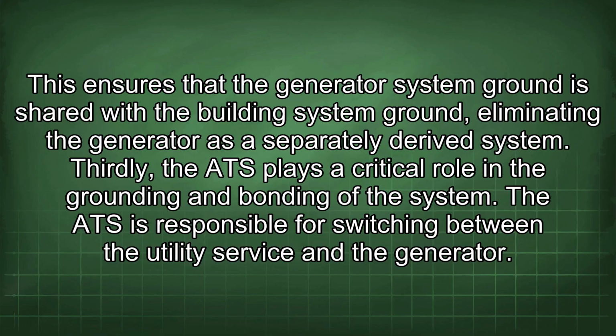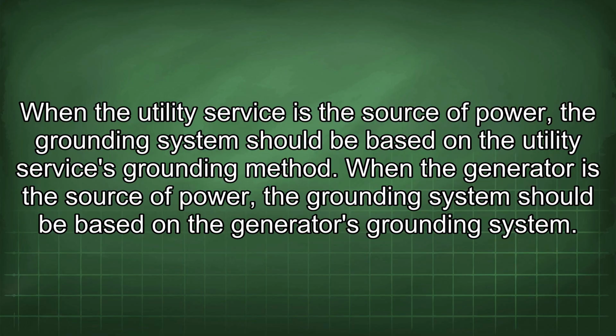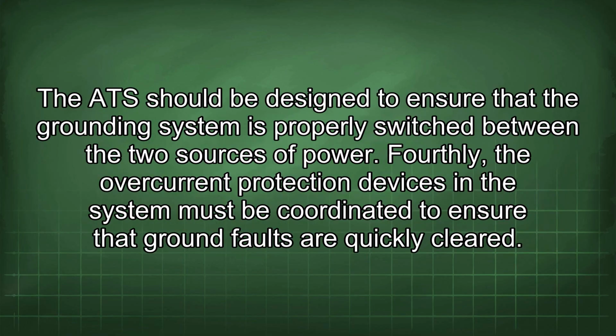Thirdly, the ATS plays a critical role in the grounding and bonding of the system. The ATS is responsible for switching between the utility service and the generator. When the utility service is the source of power, the grounding system should be based on the utility service's grounding method. When the generator is the source of power, the grounding system should be based on the generator's grounding system. The ATS should be designed to ensure that the grounding system is properly switched between the two sources of power.